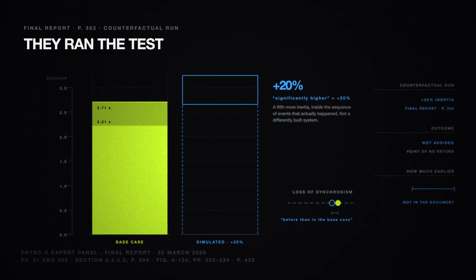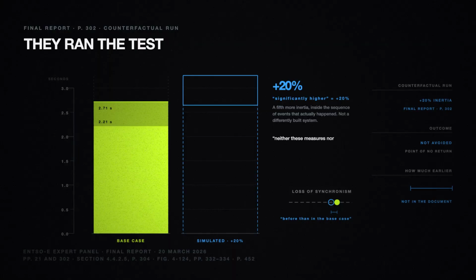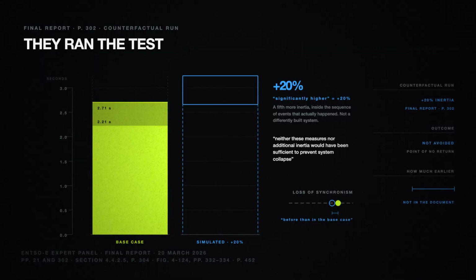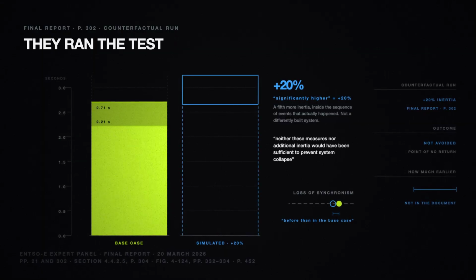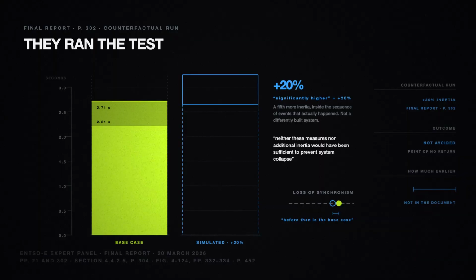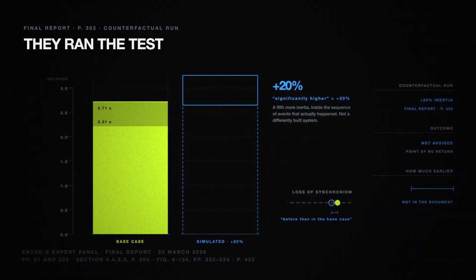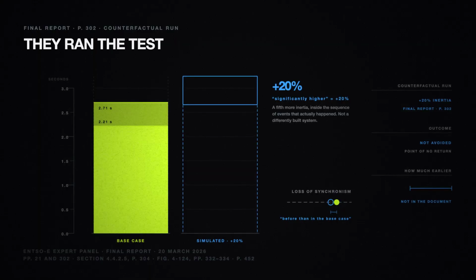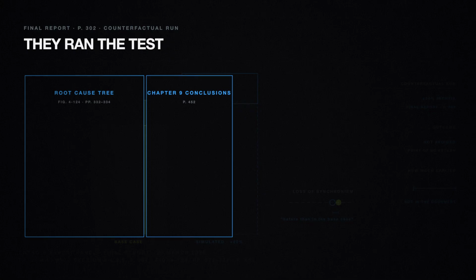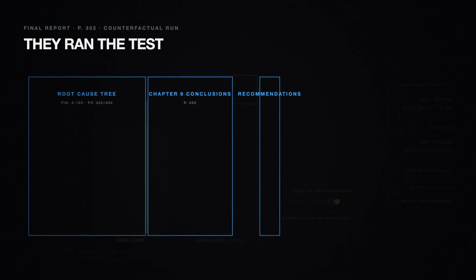And in section 4.4.2.5, even under the assumption of perfect execution of defense plan actions, neither these measures nor additional inertia would have been sufficient to prevent system collapse. Then the question of where the word ended up. Inertia does not appear in the report's root cause tree. It does not appear in the conclusions of Chapter 9. There is no recommendation on inertia levels anywhere in the document. The panel tested inertia and left it out of its answer.